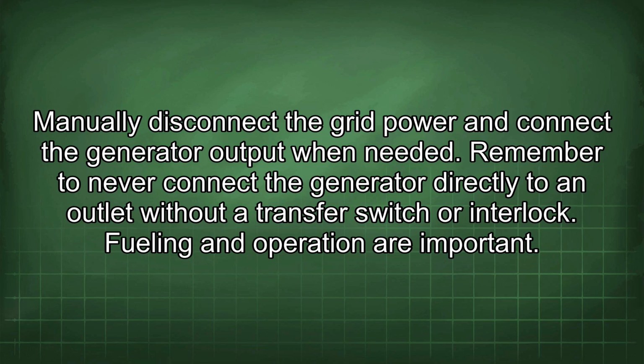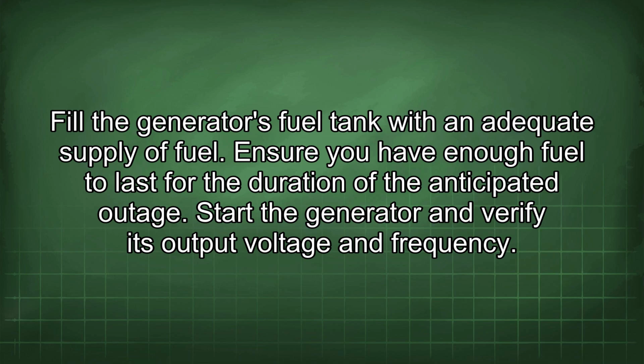Fueling and operation are important. Fill the generator's fuel tank with an adequate supply of fuel. Ensure you have enough fuel to last for the duration of the anticipated outage. Start the generator and verify its output voltage and frequency.